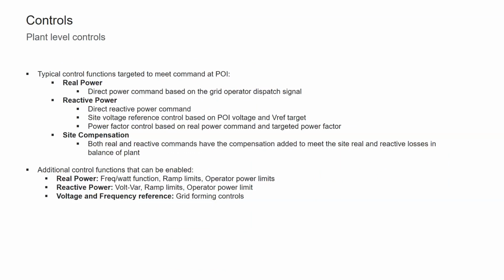On top of it, there's frequency-watt, ramp limits, things like that, which are not typical for real power, reactive power control. And if you're a grid forming inverter, there could be something the plant controller passes down as a reference, which, as the industry is evolving, could be different for different OEMs. But we see this as very typical of a plant controller.